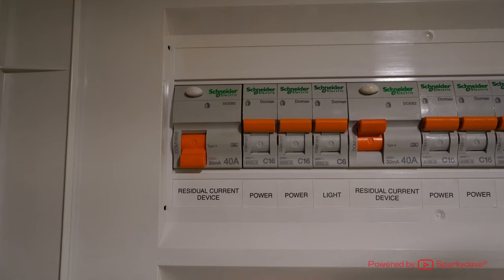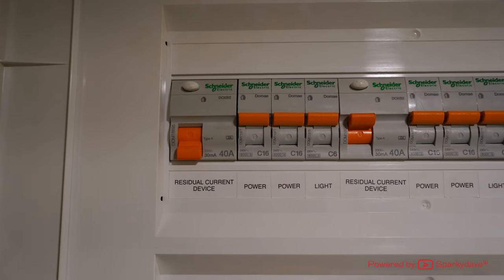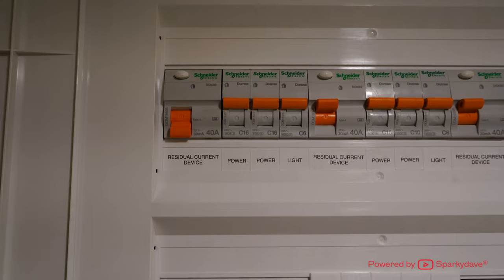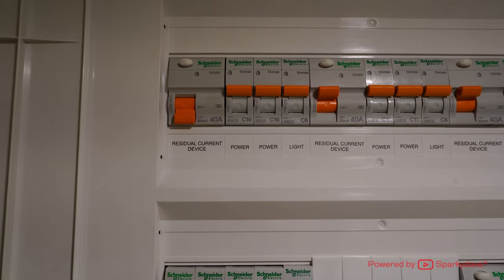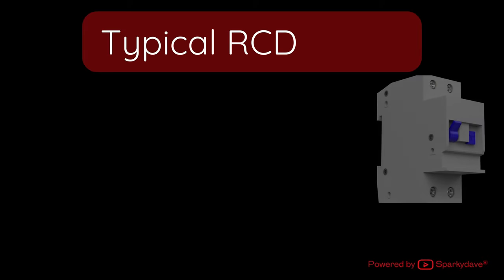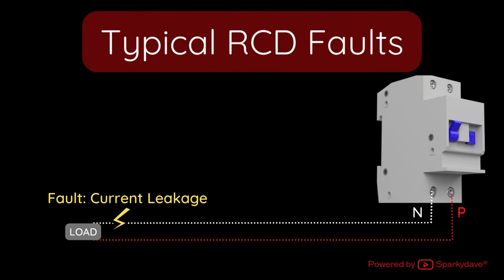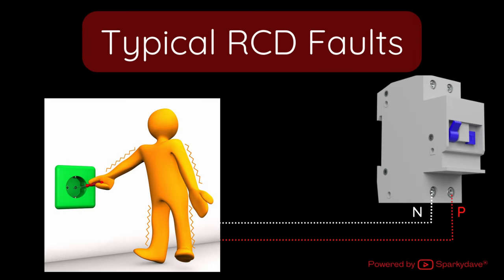Where the RCD has tripped without a circuit breaker, this would generally suggest a neutral cable connection or appliance has failed somewhere in the house. This is a typical RCD fault, which means that current is not returning through this RCD at the switchboard and is leaking out of the circuit. The fault is likely an electric shock hazard for a person, given the RCD has operated.